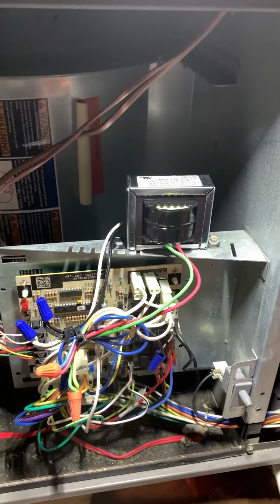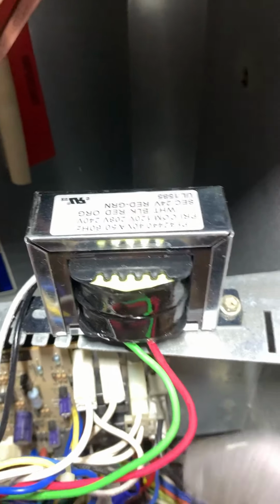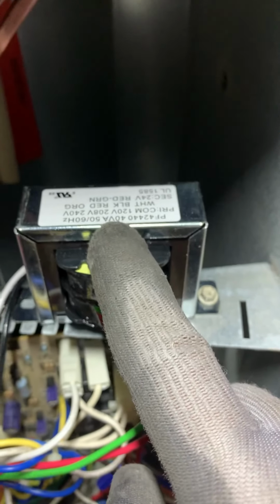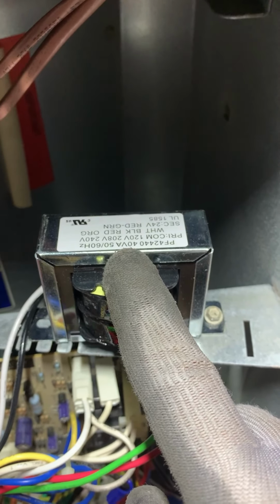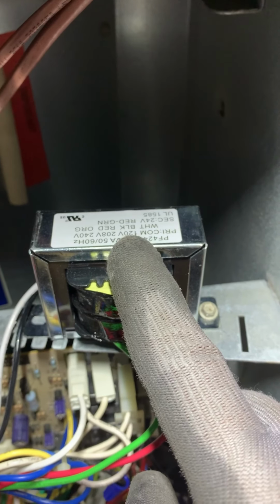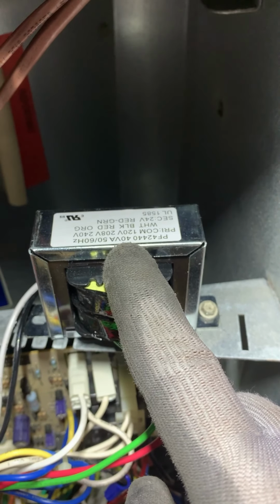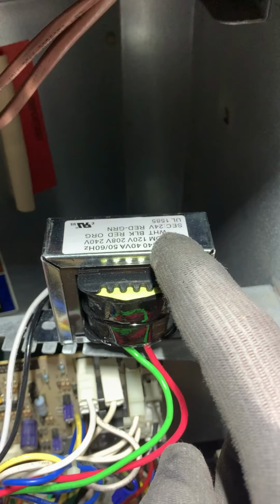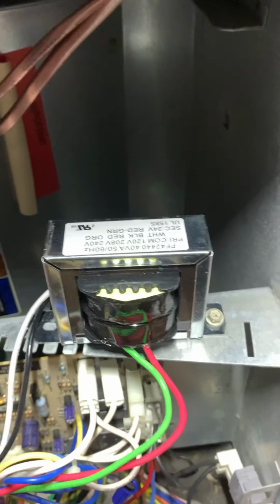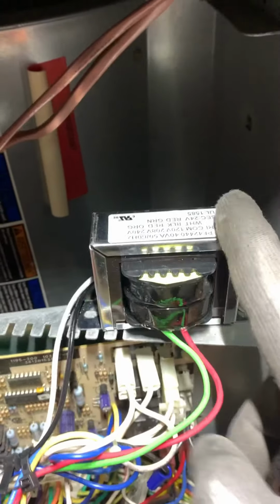We'll see what's drawing this up. Now, in order to see how many amps a transformer could have, you've got that 40 VA right there, by the secondary, which is 24 volts. So if we divide the 24 into 40, that'll give you how many amps this transformer can handle or hold.